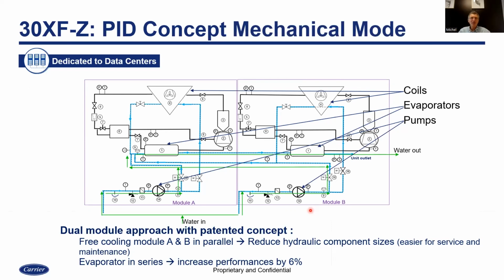So generally speaking, I will just very quickly go through with you how water flows. I have put some arrows here. So water enters and goes to two modules. Each of the modules, by the way, has its pump, which basically operate in parallel. If you are following the green part, this is the case of what we call mechanical cooling, so there is no opportunity for free cooling. They join together at this point and then enter the first evaporator, the second evaporator, and leave the machine.